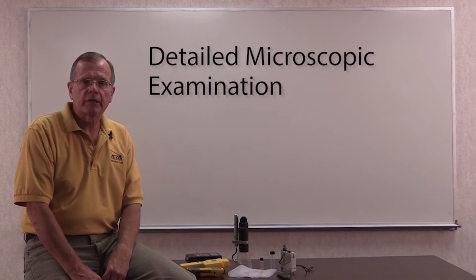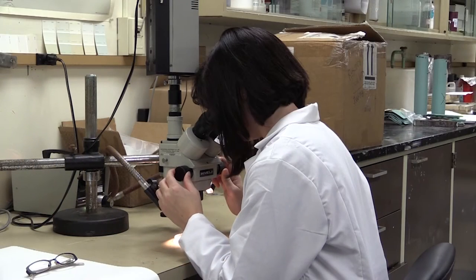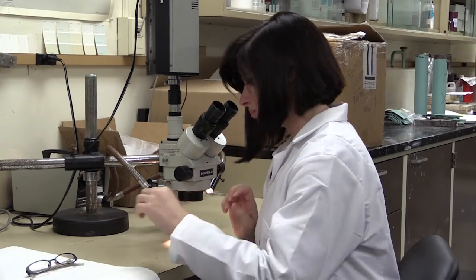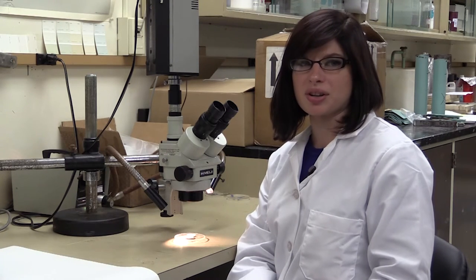Detailed microscopic examination was performed to determine the number and thickness of the coating layers, as well as to determine the plane of failure, and to look for the presence of other contamination or objectionable properties. The laboratory microscopic examination revealed the presence of five coats. Often when coating layers of the same color are applied in succession, it is difficult to differentiate between two layers of the same product.